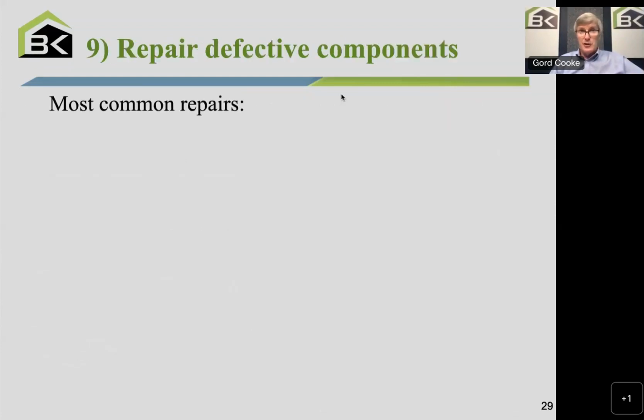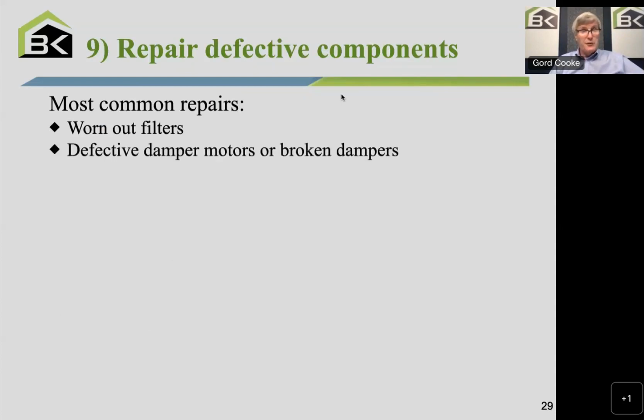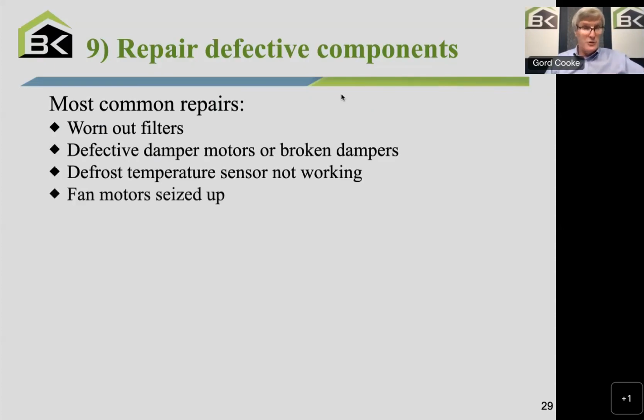And then as we start to finish up, any items that need repair. The most common one is worn out filters. I already said every 3 to 5 years you're changing filters. Defective damper motors are the next biggest thing to go. The dampers may be swinging loose, not moving correctly. You have to replace that damper motor or a broken damper. Third, the defrost temperature sensor not working correctly. What you're going to find is the unit's worked fine for the last 3 or 4 years, and all of a sudden it turns cold, and I'm seeing the unit frosting up. That could be the temperature sensor not working. Again, check the manufacturer's instructions on how to diagnose that.